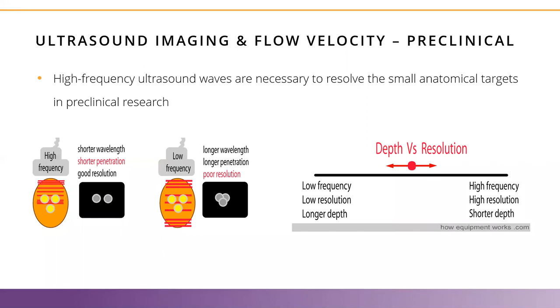Here you see the effect of high frequency and low frequency. With the high frequency, you will have a very good resolution. However, the penetration depth is lower, thereby not seeing this third spot. While with a low frequency, the ultrasound can travel further into the body, whilst you will have less discernibility. So there is a clear balance between depth and resolution when using ultrasound imaging. And that also translates to Doppler flow velocity measurements.